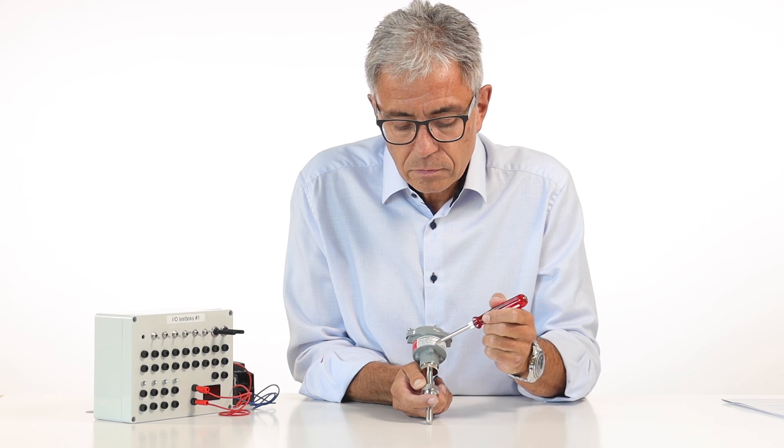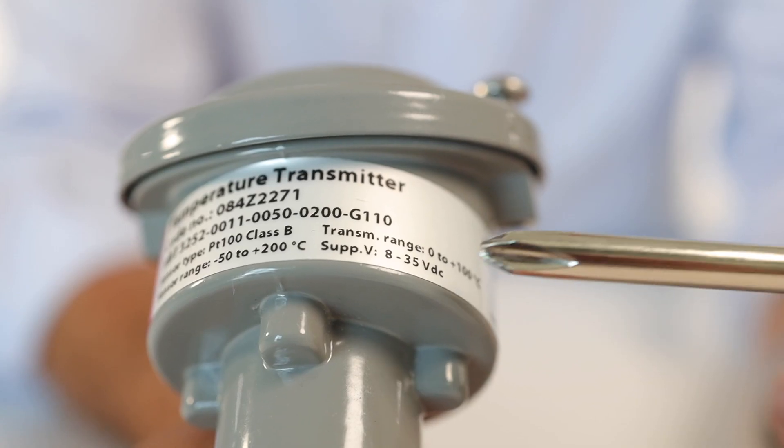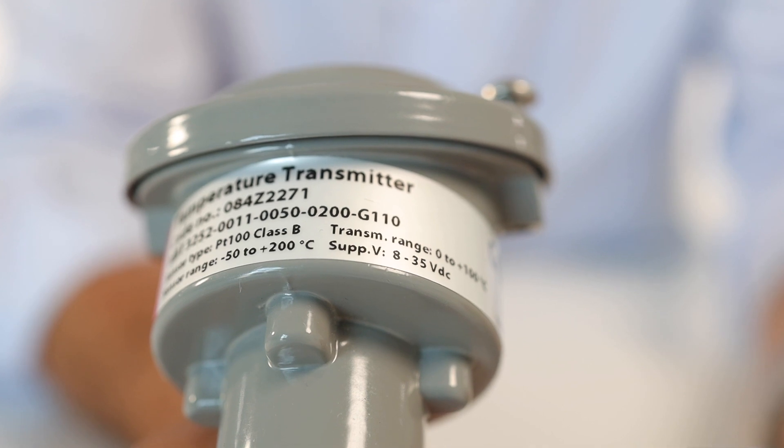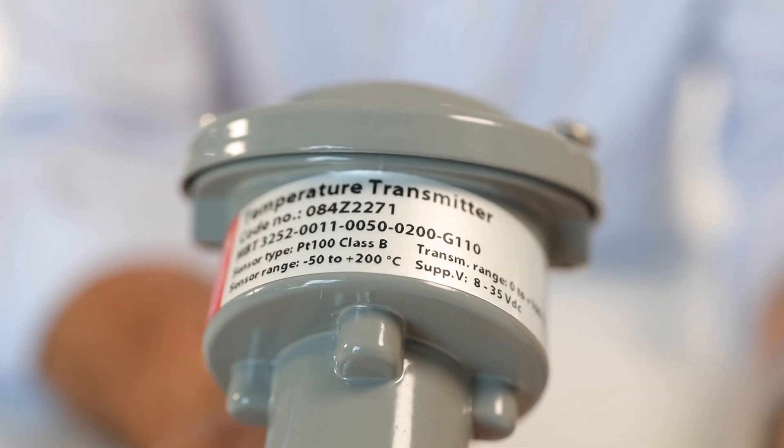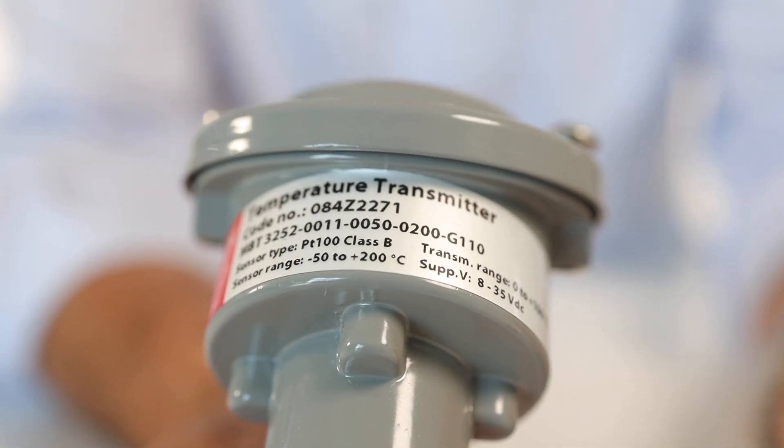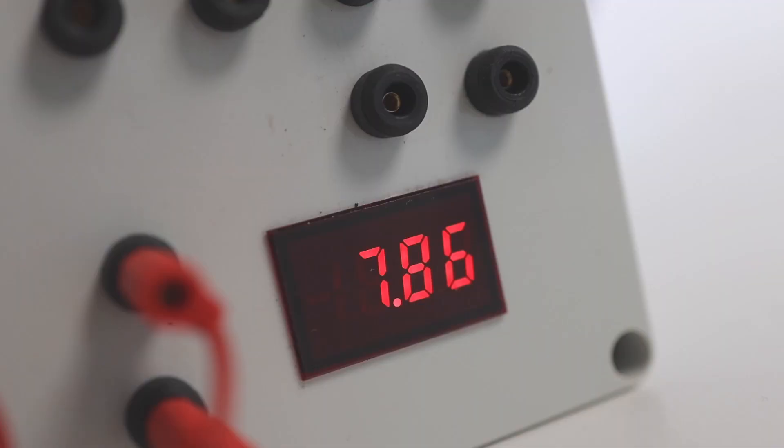We'll demonstrate how to install a Danfoss temperature transmitter with 8 to 35 volt DC and an output signal of 4 to 20 milliamps. To read the output, we'll use a milliamp display.